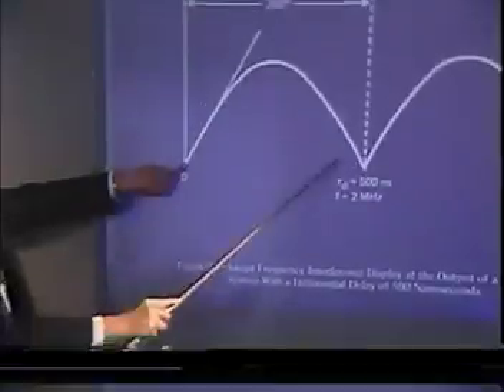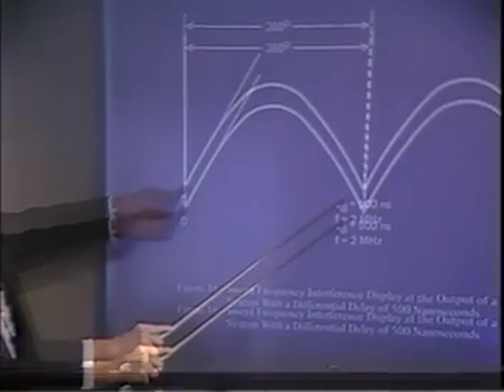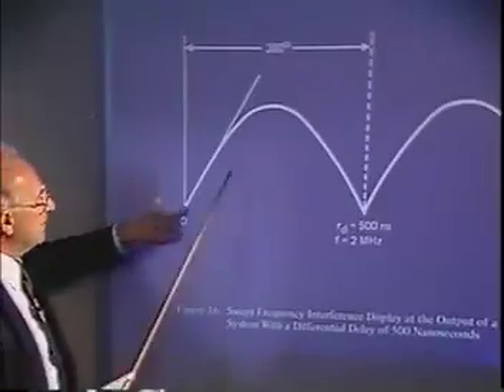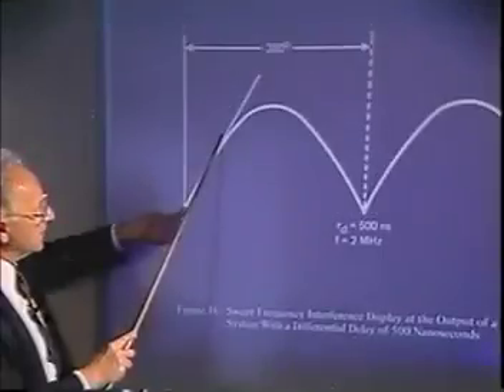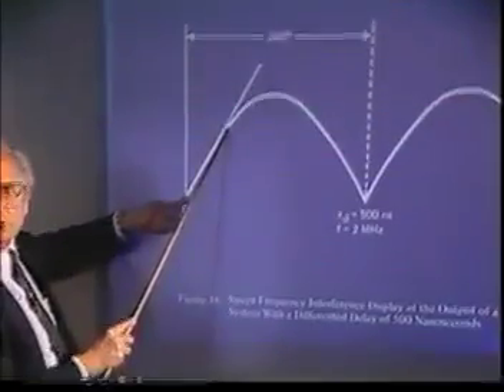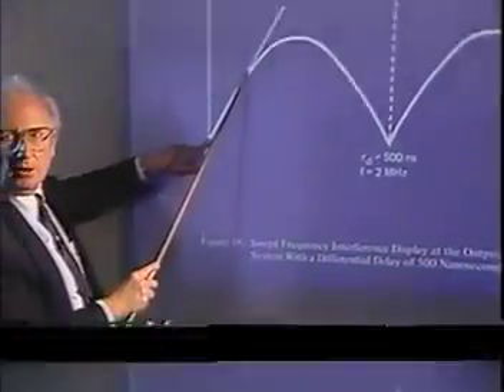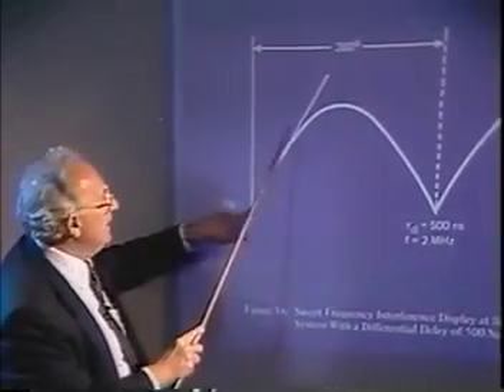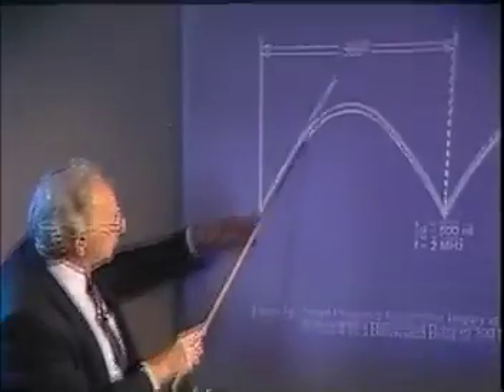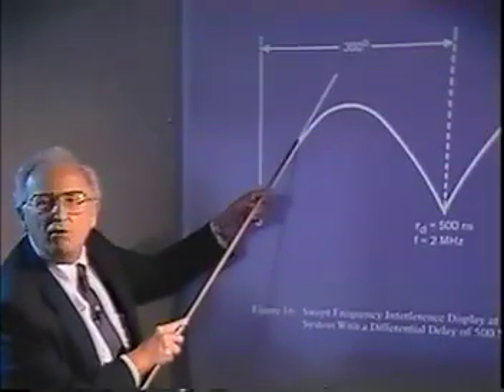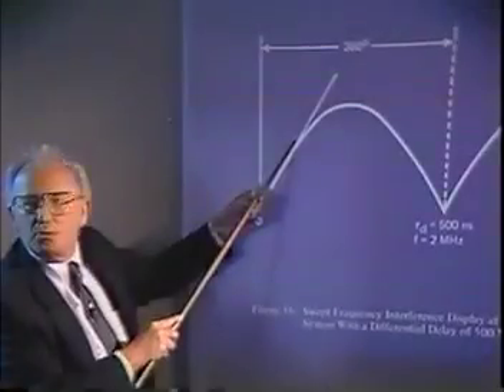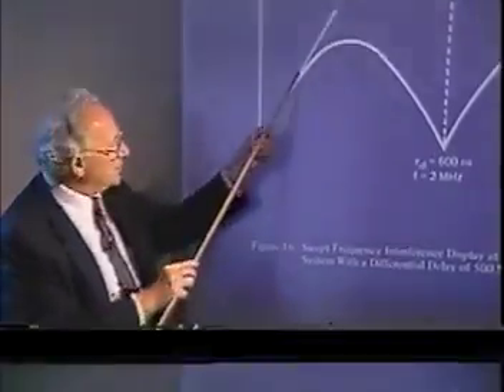Now this is a linear plot. I'm going to make this a logarithmic plot in the actual measurement, but keep in mind that the logarithmic plot is still going, so only 30% of this is what we're going to be interested in if we don't make a correction. By that I mean that you're going to calibrate this between here and here, you see, so you know how many volts per hertz you would have in the system, because this is the slope of the discriminator.